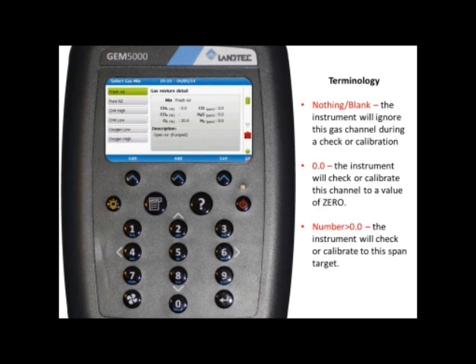Let me explain. If any channel has a value of 0.0, like in this case for the CH4 and CO and H2S and H2, if it's a plus unit, the instrument will check or calibrate this channel to 0. If the gas channel is blank or has no value at all, the instrument will ignore this gas channel during a check or calibration. And in the case where any gas channel has a value greater than 0, like the oxygen at 20.9, the instrument will check or calibrate to the span target shown, in this case to 20.9.